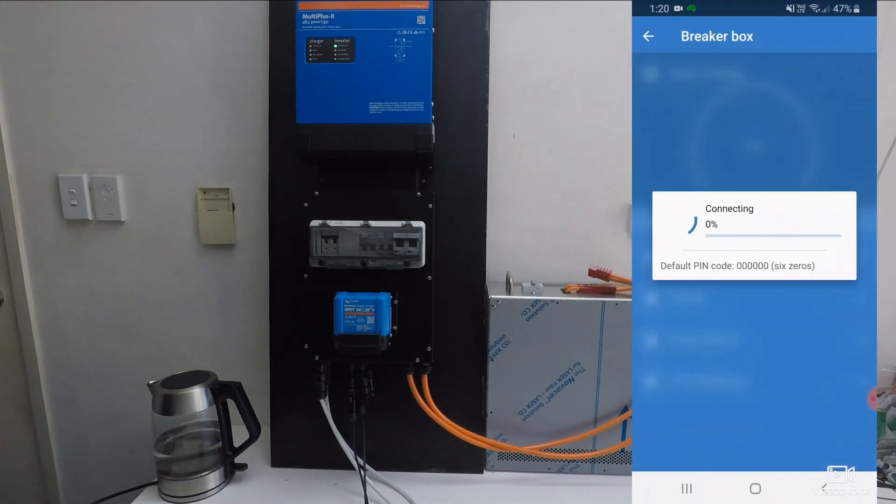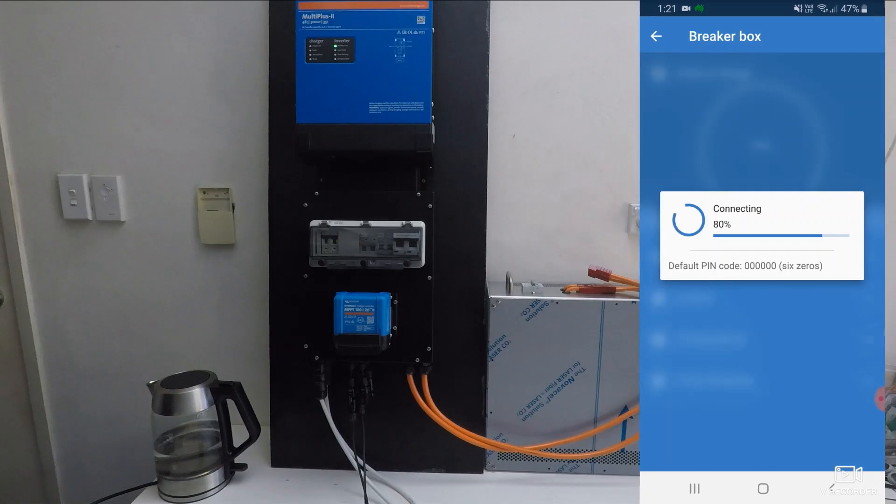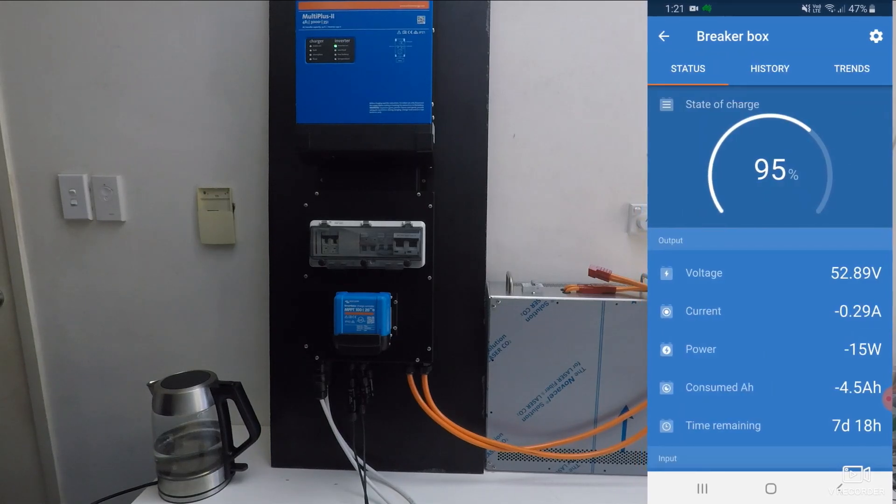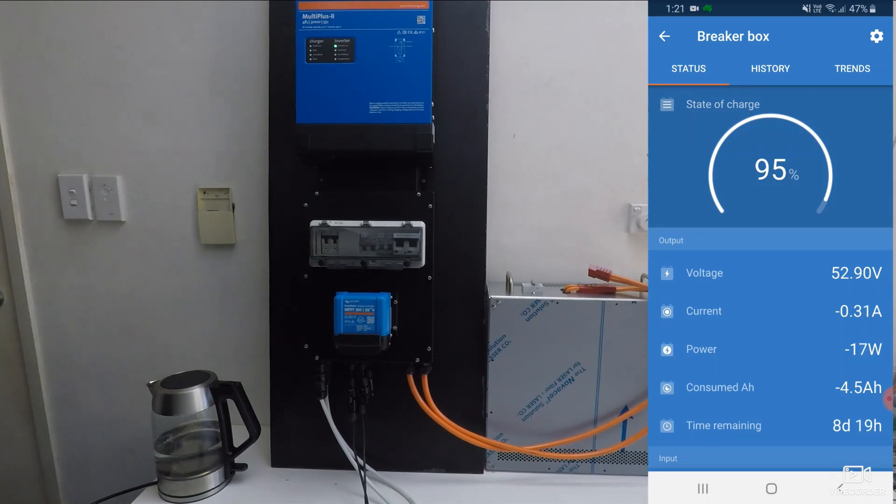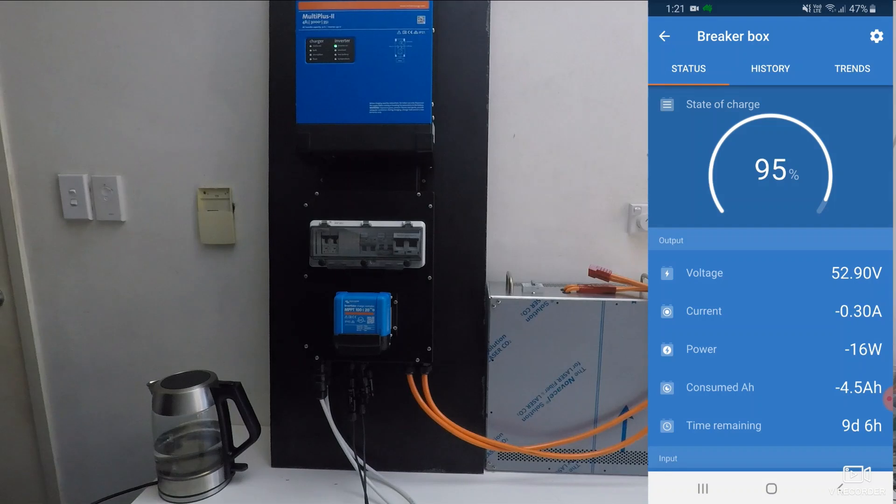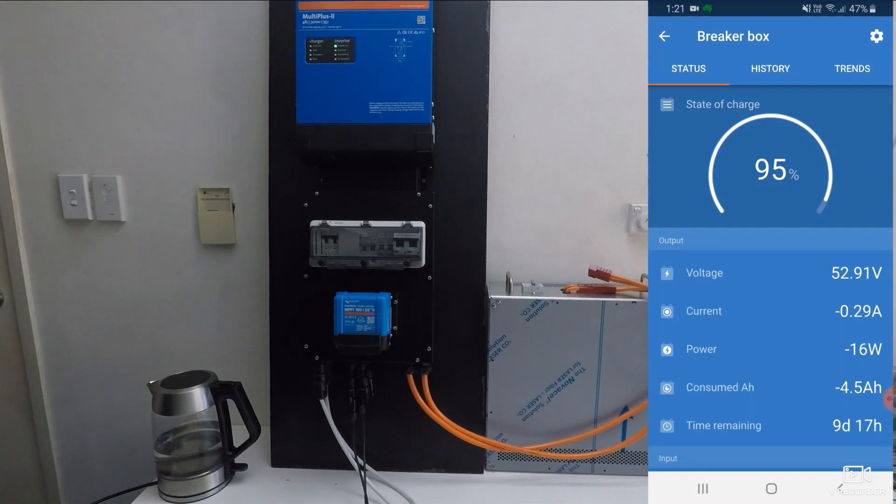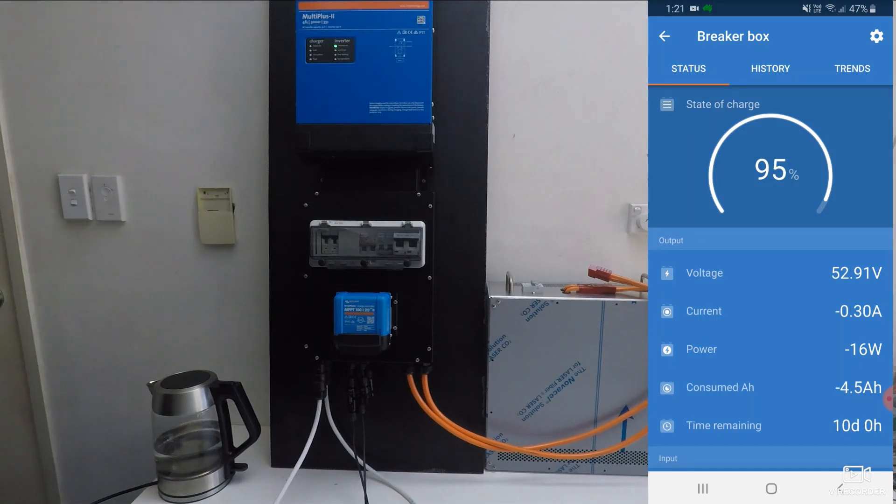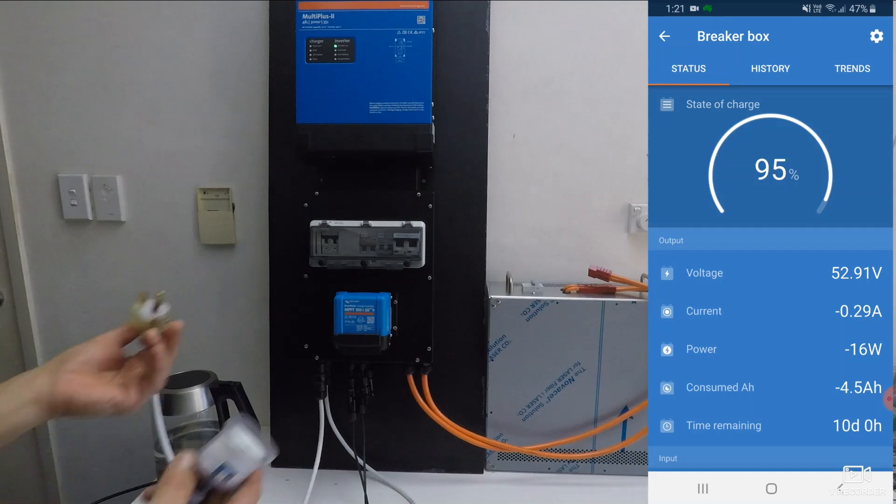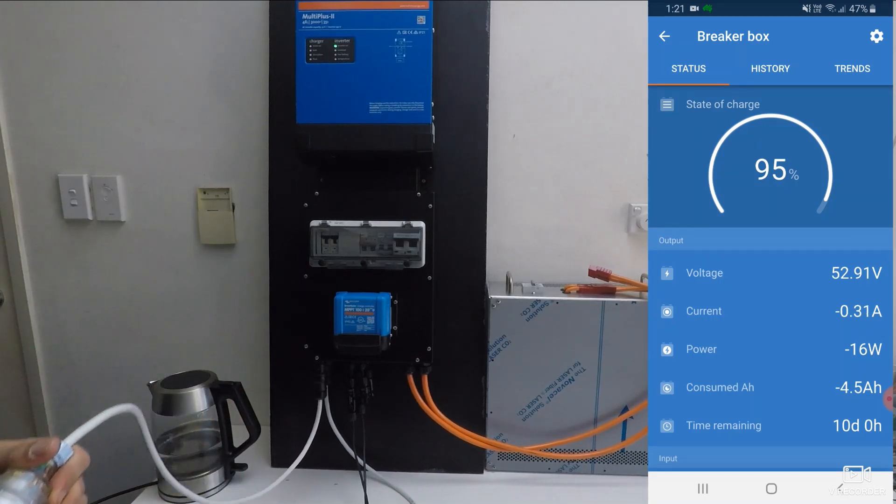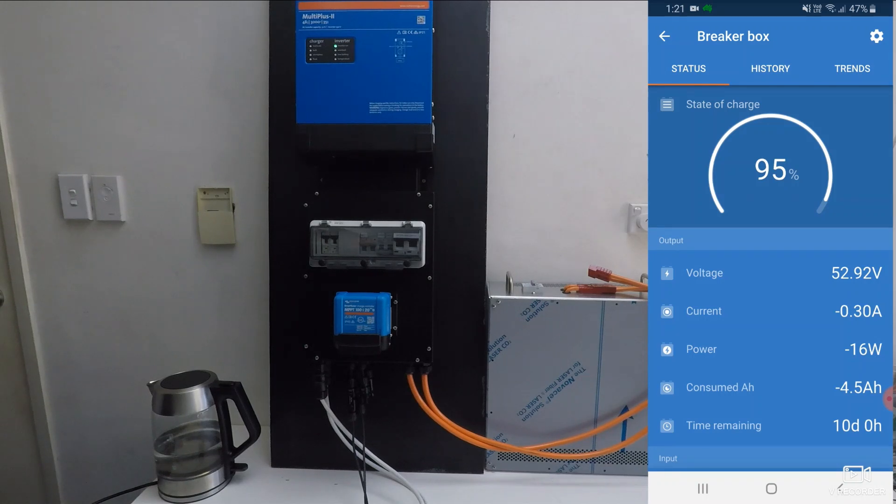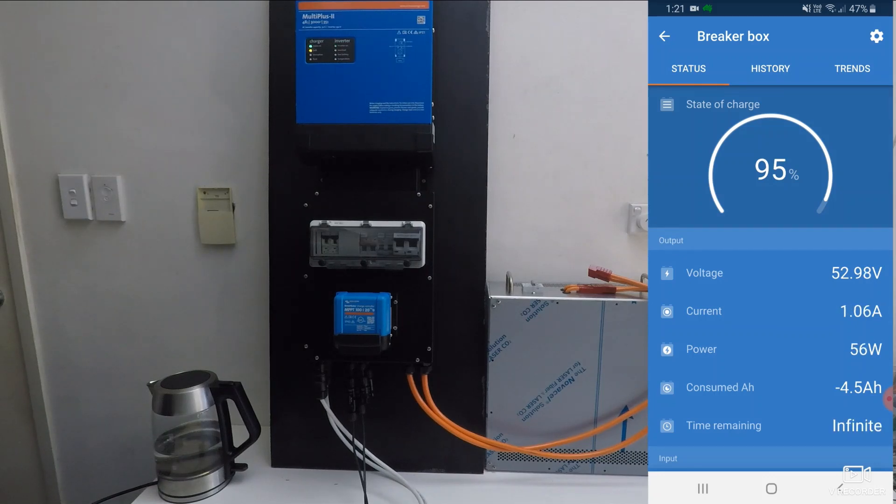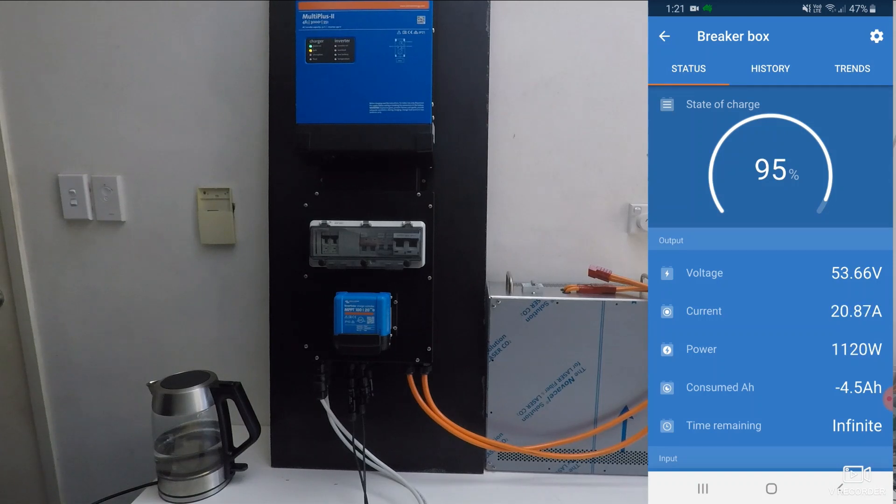So we're going to go to our VictronConnect and connect to our breaker box so we can see it. At the moment we've got the solar off to simulate being in the middle of the night where there's no sun. So at the moment we've got 16 watts going out. Now we can program your MultiPlus to whatever current level you want it to be. If you've got a very small generator we can limit the current not to overload the generator, or if you've got a large generator we can turn the current up so that you charge faster, and also transfer the loads from the inverter to the generator. So if we just plug in to a normal lead, this is a power source, it's exactly the same as the generator. The inverter will wait 30 seconds to make sure that the power quality is good. I recommend an inverter generator if possible, as the power is very clean and easy to connect to. The inverter will protect itself and any loads if you have really dirty power.